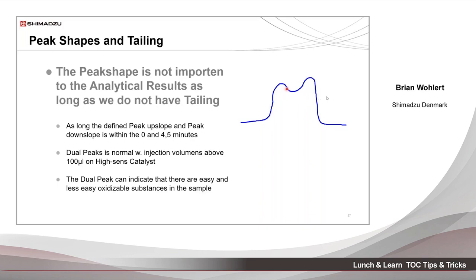The peak just has to be within 0 and 4.5 minutes, and then it will be detected as a peak. It has to have a specific upslope and a specific downslope to be detected as a peak.